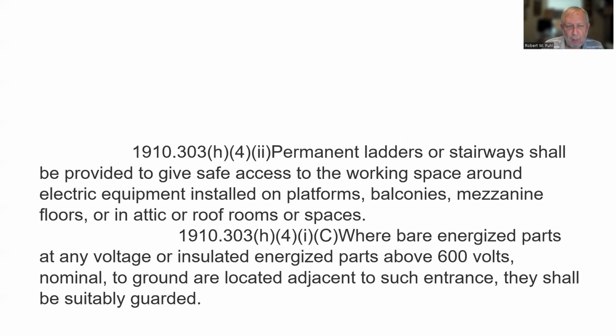Permanent ladders or stairways shall be provided to give safe access to the working space around electric equipment installed on platforms, balconies, mezzanine floors, or in attic or roof rooms or spaces. So, permanent ladders or stairways. Where bare energized parts at any voltage or insulated energized parts above 600 volts nominal to ground are located adjacent to such entrance, they shall be suitably guarded.